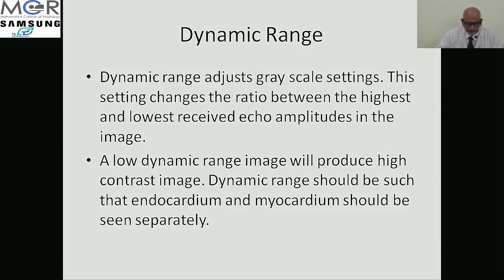Now, dynamic range adjusts grayscale settings. These settings change the ratio between the highest and the lowest received amplitude. So a low dynamic range image will produce high contrast images.